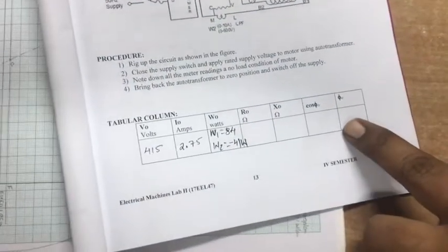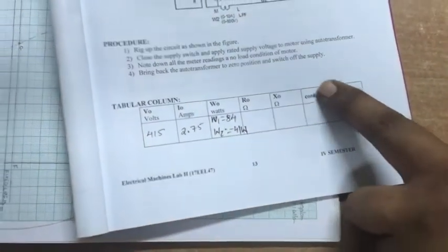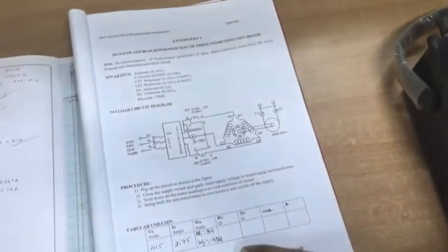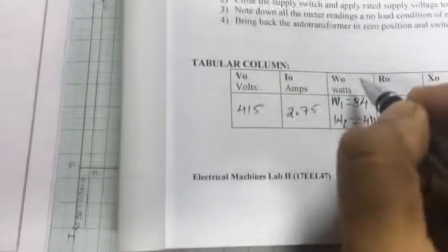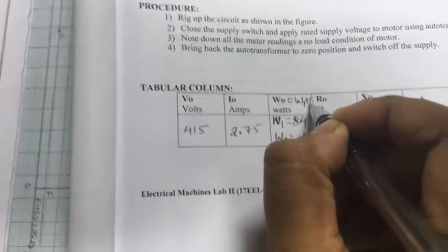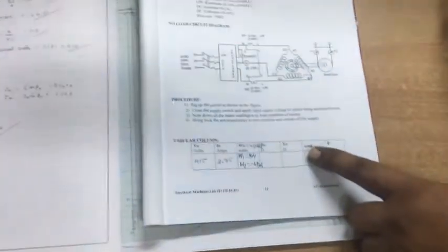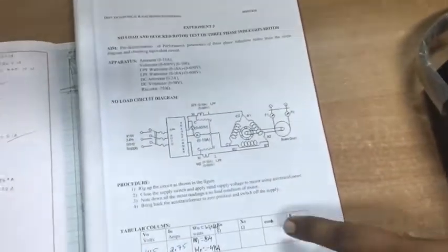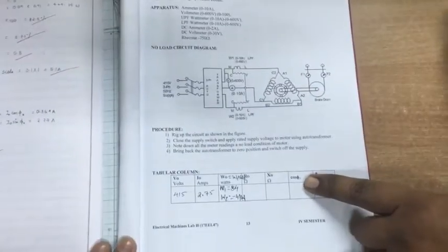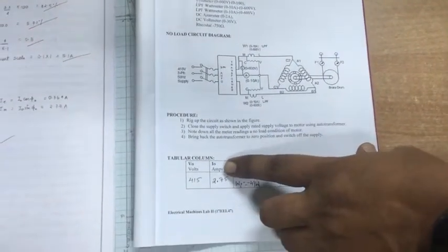Now with respect to these values, calculate R0, X0 and cos phi naught. Cos phi naught can be calculated with respect to the power formula, W0 is equal to root 3 V0 I0 cos phi naught. Similarly, the no load resistance and no load reactance can be found by knowing the power factor cos phi naught and the no load current.